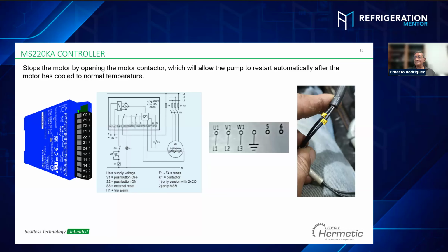Pump. Yes, and exceed the capacity of the motor, or the mass flow capacity of the motor. And maybe cavitation, and many factors can affect it. So what we want to do as a technician, we want to take our amp clamp out, put it on the motor, and look at the rating plate that you guys put on that motor. If we're going over that, that is going to cause those resistors to increase in resistance, send a signal back to this controller, and open up the circuit to shut it down. Correct.